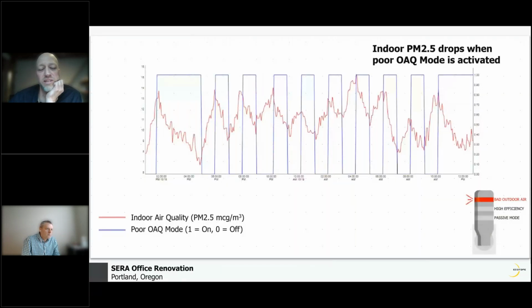So this project was designed around a design for off approach. There's been some earlier sessions around that, but essentially if the outdoor air is adequate for conditioning, we turn everything off and we open windows. And that's a passive mode. Then we've got high efficiency mode whenever we need heat or cooling. And then we've got a third mode called OAQ mode, or bad outdoor air mode, as it's labeled here. It looks at the outside air, and says, if the levels of PM 2.5 are higher than about, I think it's 14 is our threshold, engage this system. And we can see in the graph, when it engages, we watch the indoor PM 2.5 drop. And so it just cycles like that as needed.